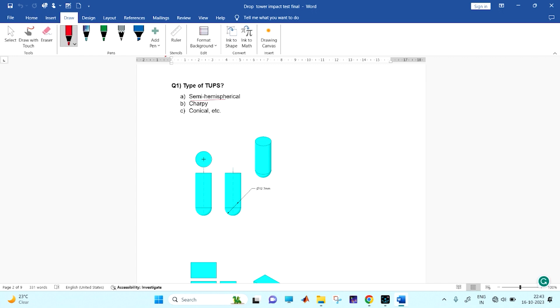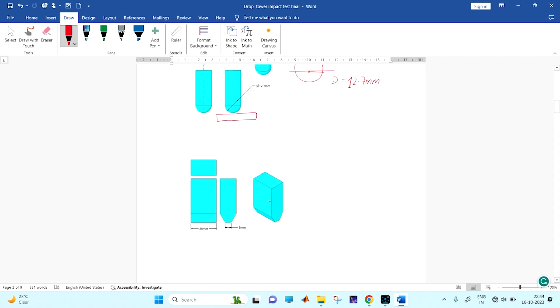We are going to see the different types of tups. The first type is the hemispherical - the tip which is going to strike the specimen is hemispherical, actually it is part of a sphere, and its diameter is 12.7 mm. Similarly, we have another tup which is the Charpy tup - that is actually a trapezoidal type of tup. It is having 20 mm in width and 5 mm in front width.